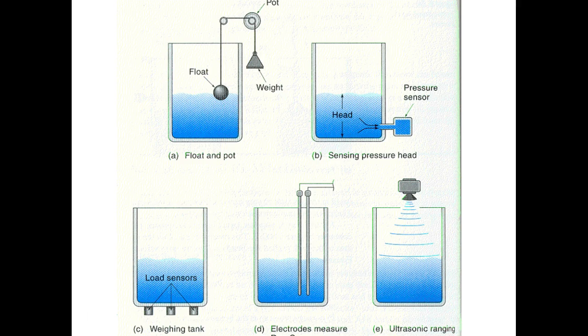Electrodes are very popular too, either resistive or capacitive — like airplanes use capacitive. We could also use pressure: how much liquid we have above, if we put a pressure sensor down here, the pressure it generates would give us the level. But that varies with density too. If I'm measuring the same liquid or material, I can do weight or pressure — if I know how much it weighs per cubic foot, I can figure out the actual level just by measuring the pressure or the weight.